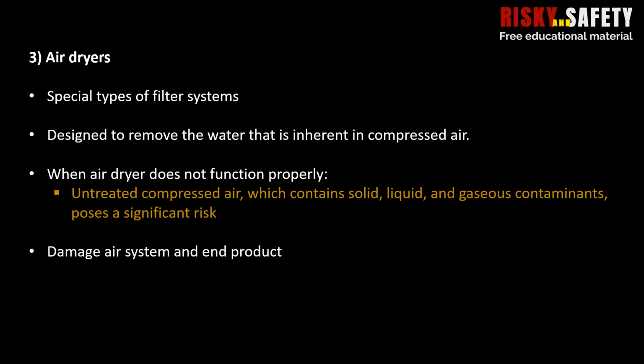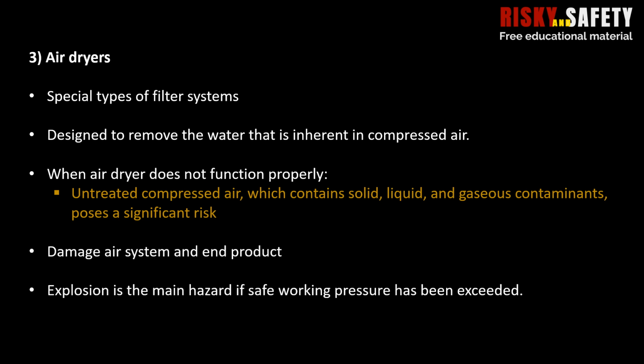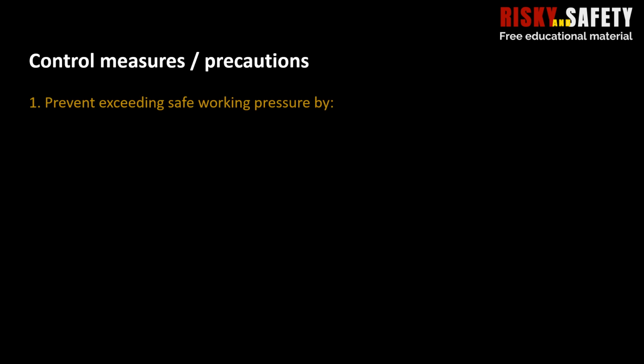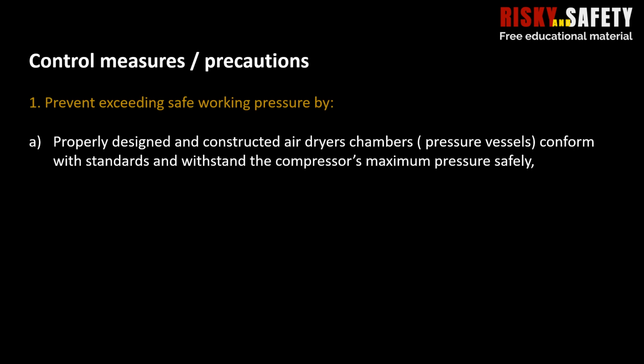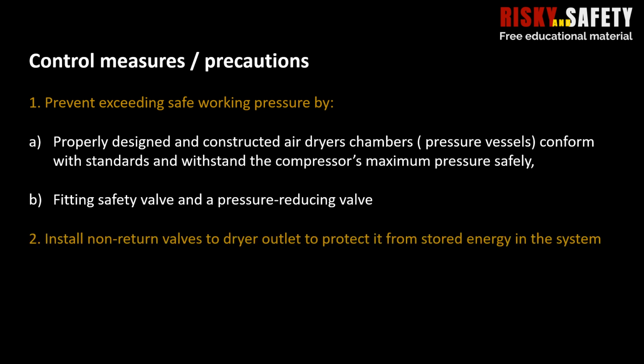The associated hazards are similar to those of air receivers, so explosion is the main hazard if the safe working pressure has been exceeded. You can control the risks by preventing the safe working pressure from being exceeded, through properly designed and constructed air dryer chambers that conform with standards and withstand the compressor's maximum pressure safely. Fit a safety valve and pressure reducing valve, and install non-return valves at the dryer outlet to protect it from stored energy in the system.